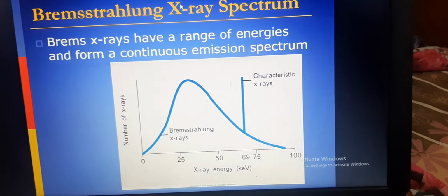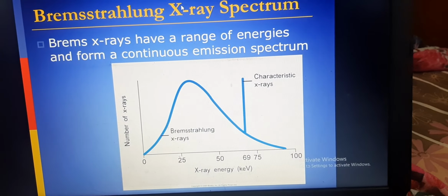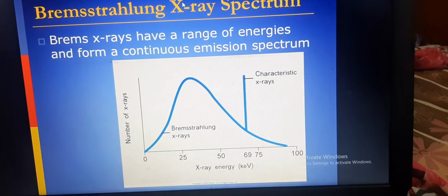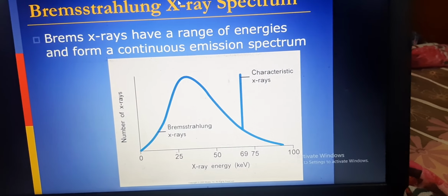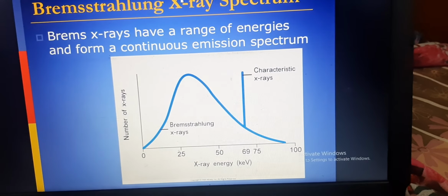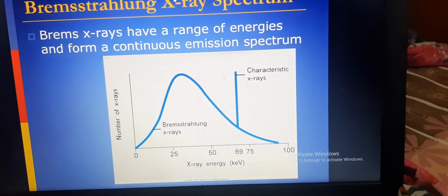The maximum energy that an X-ray can have, in numerical value, is only the kVp operating. That is why we call it kilovoltage peak. What is the maximum voltage a machine contains?